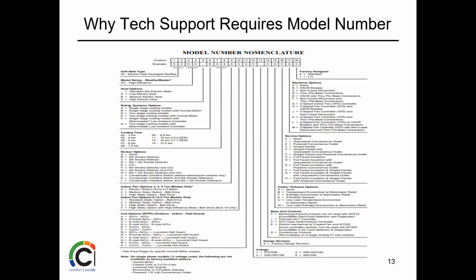And again, here I talked about that. So you can see that every digit there has a purpose. The biggest one we look for, obviously, is the size. So 7 and 8 tells us what size you're working on. Then the other one we look at is number 14. So what kind of controls are you using? You know, is it a building management system, or just some sort of thermostat control? And then, of course, the power that you have. What's your voltage? Are you 208, 460, 3-phase, whatever? So that's where that comes in. It just saves a lot of time, so we don't have to get into all that.